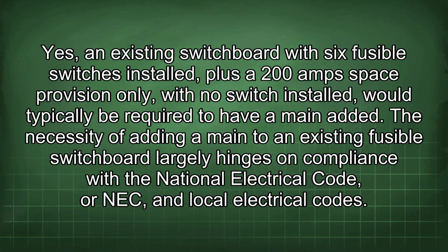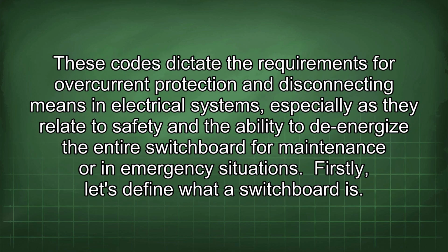Yes, an existing switchboard with 6 fusible switches installed, plus a 200 amp space provision only, with no switch installed, would typically be required to have a main added. The necessity of adding a main to an existing fusible switchboard largely hinges on compliance with the National Electrical Code, or NEC, and local electrical codes. These codes dictate the requirements for overcurrent protection and disconnecting means in electrical systems, especially as they relate to safety and the ability to de-energize the entire switchboard for maintenance or in emergency situations.